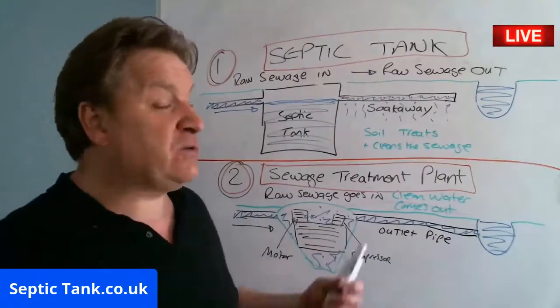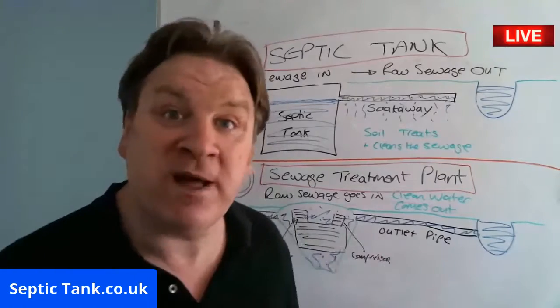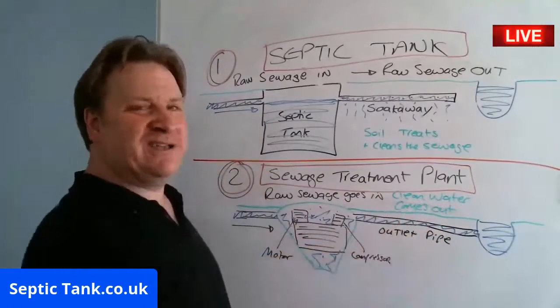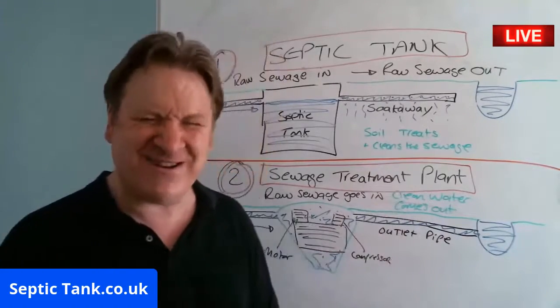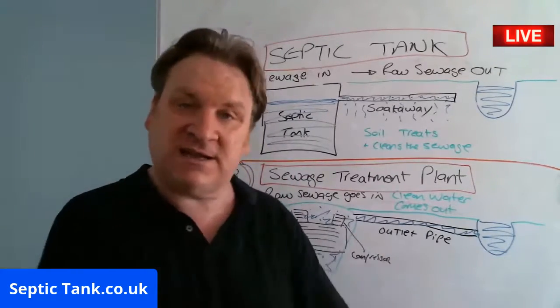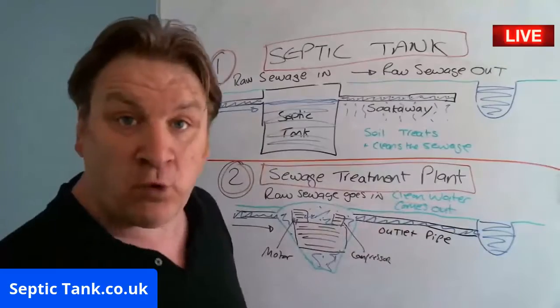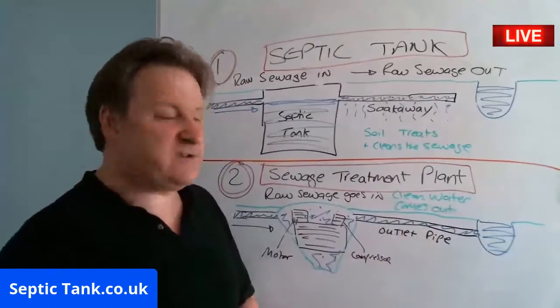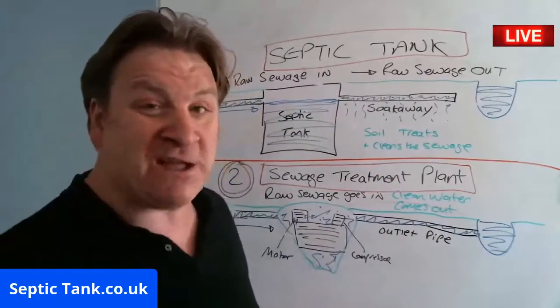However, if you don't live by a water course or river — say the stream is half a mile away — then a sewage treatment plant is overkill. You don't need to spend 1,500 quid a year on electricity bills and 300 quid a year to have it serviced. If you don't live by a water course, a septic tank and soak away is going to be fine.